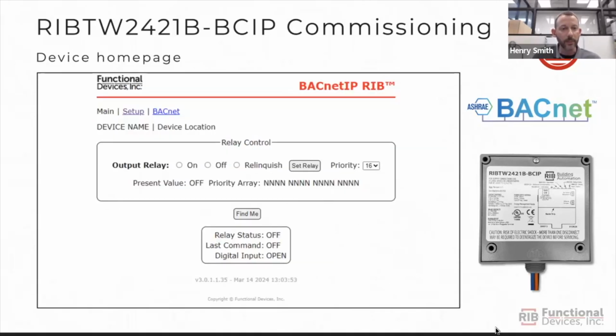The first web page you would come to is the main page. It shows you the status of the relay. It allows you control over a browser for turning the relay on or off, and at which priority you would want that binary output commanded at. You also have a Find Me button, and when that's pressed, the blue LED on the top of the unit would flash rapidly. It's just a good way, if you've got a few of them on your bench or you're trying to commission several at once, it just allows you a visual aid of which one you're actually communicating with. And down there at the bottom of that page, you see the status of the relay output, as well as the last command it received, and then finally the state of the binary input.